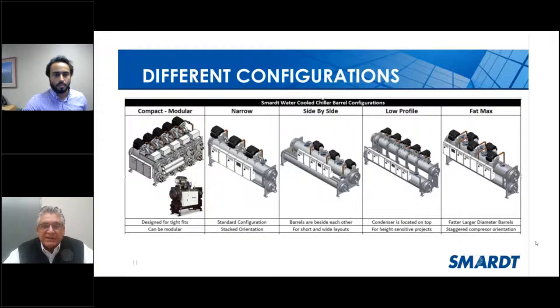The more traditional arrangement is a narrow configuration. You see the one next to the right. As the tonnage increases, those barrels get assembled side to side, a more traditional centrifugal chiller approach. Again, Smardt is a centrifugal grade chiller. The difference is it uses oil-free technology. But also, if you look at any centrifugal chiller, its capacity is based on the speed of the impeller, the circumference of the impeller, and the tangential force it can put on the outside of the volute, right? So by having multiple compressors, you get some redundancy. You also get higher efficiency at part load. But they also have an opportunity to look at how to do all those things and get high lift with a machine that's somewhat limited in circumference. We'll talk about that in just a little bit, okay?